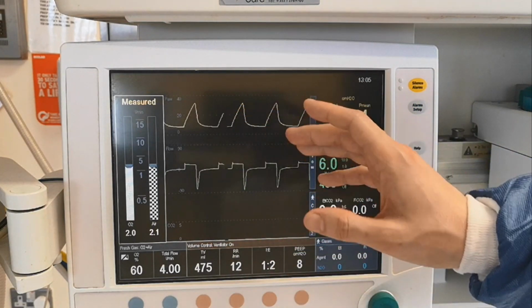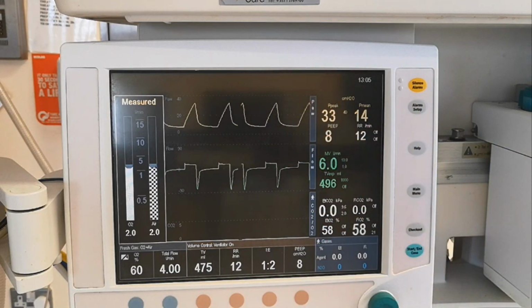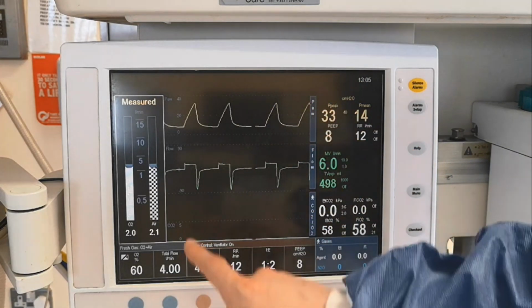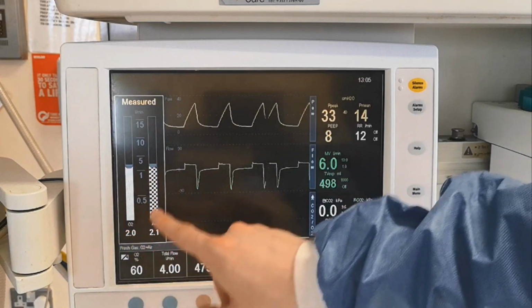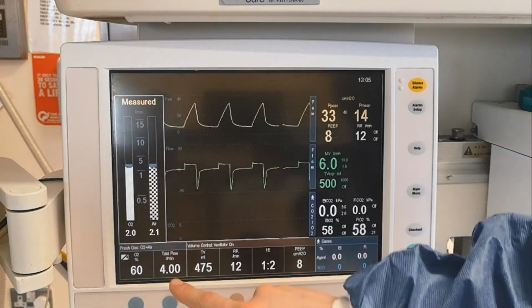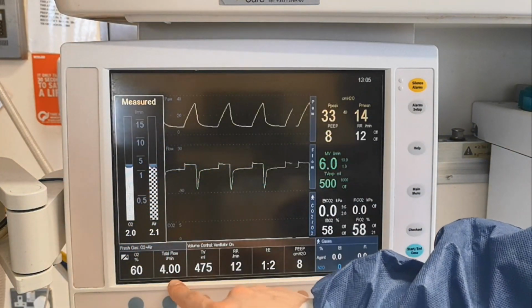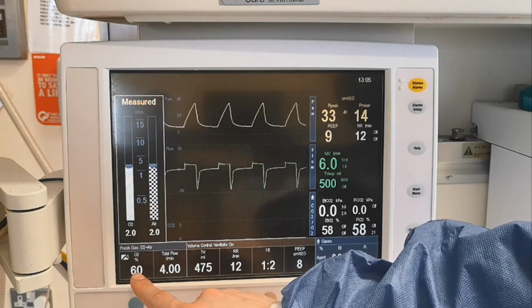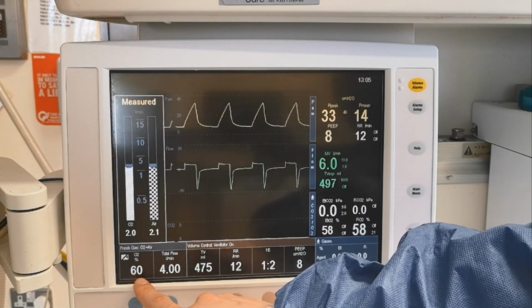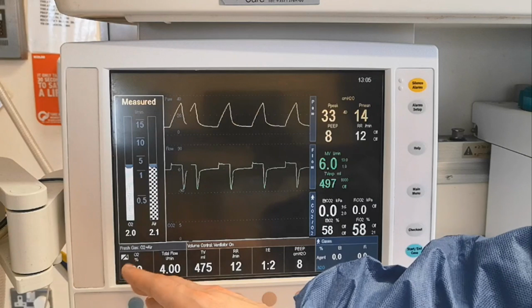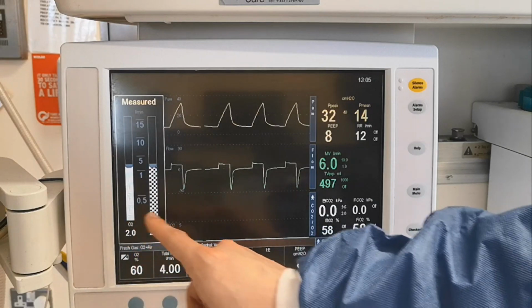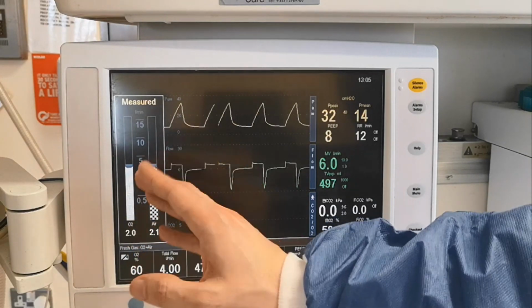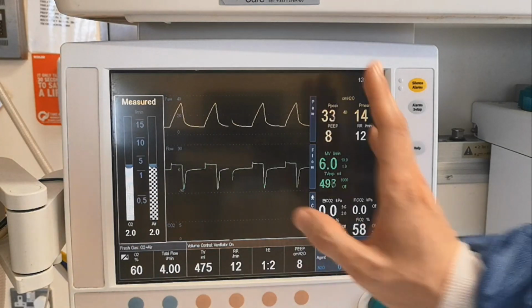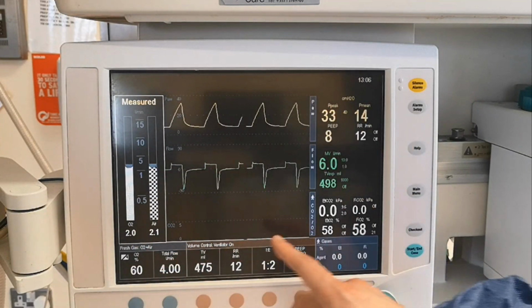So that you're not intimidated by these curves. This is the mixture of gas that we're giving. So here we have 4 liters, and we're giving, all right, 60% or 50% of oxygen. Then the machine will divide it 50% or 60% air and oxygen. Let's just leave it there for a second.